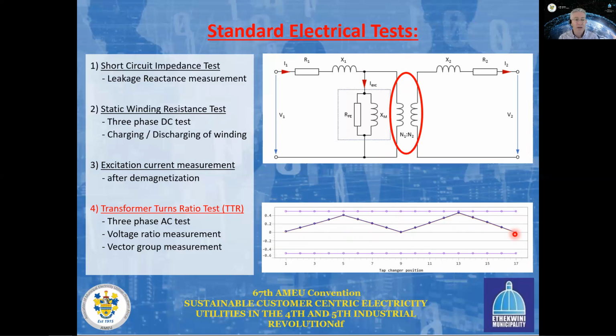These are the 4 standard electrical tests that we suggest for any transformer, be it a 400 kVA small little distribution transformer all the way up to a 20 or 40 MVA transmission type transformer. And these tests, even for a transmission type transformer, should take you no longer than an hour to conduct. That includes even setting up, connecting the leads, as well as generating the test reports afterwards. It's really a very quick test and a very useful and very conclusive test in terms of the health of the electrical parts of this transformer, in terms of the windings and the tap changer inside that transformer.